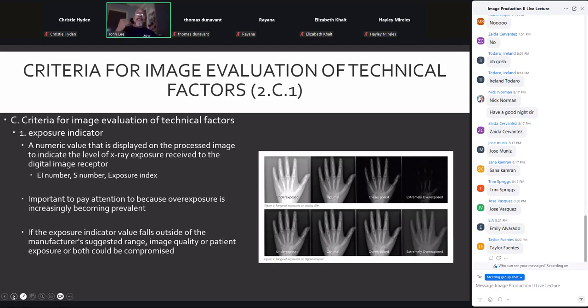So they're guidelines to help you with exposure, because with film, if it's underexposed, it doesn't look good. If it's extremely overexposed, it doesn't look good. And you had all sorts in between, optimal and overexposed. But when we get to digital, aside from the noise at underexposure and the saturation where we lose contrast at extreme overexposure, you really can't tell the difference between overexposed and optimal. And this is where dose creep comes into play. So the EI, the exposure index, is there to guide you as a technologist in your techniquing for future exams.